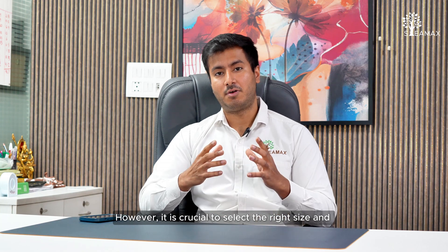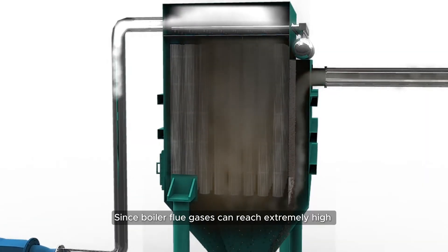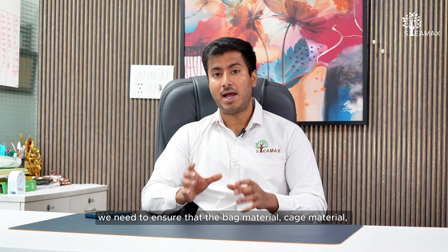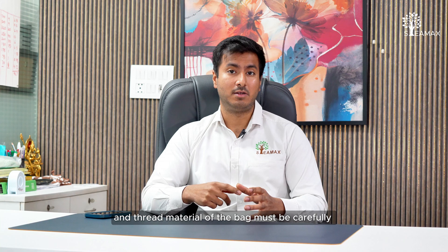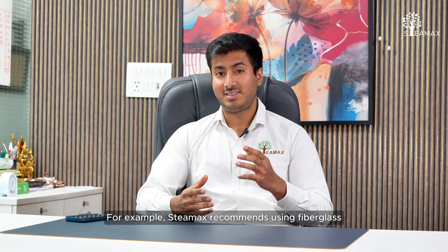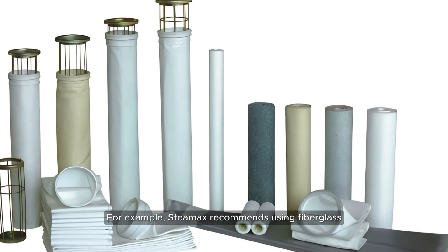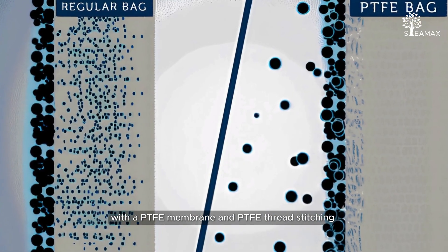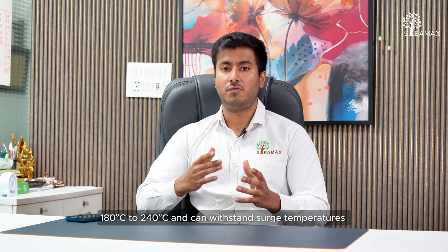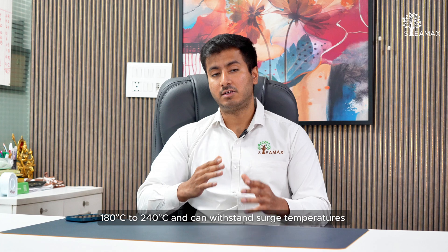It is important to ensure that the right size and material are selected for the bags. Since boiler flue gases can reach very high temperatures, the bag material, cage material, and thread material must be appropriately selected for long bag life. For example, Steamax recommends using fiberglass with a PTFE membrane and PTFE thread stitching for bags used in biomass fired boilers. These bags have an operating temperature between 180 to 240 degrees Celsius and can sustain a surge temperature of up to 270 degrees Celsius.